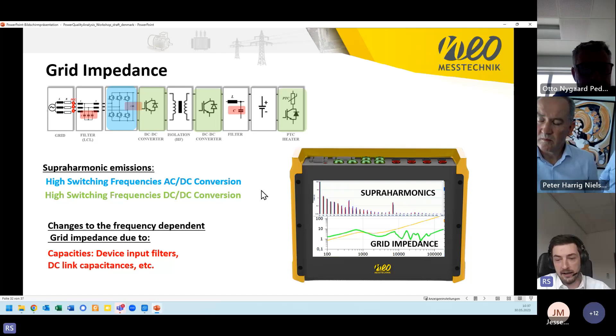I think this brings me more or less to the end, to my last slide. Regarding the energy source and the different power generation technologies—inverter, asynchronous or synchronous generators—we have power quality parameters like harmonics, unbalance, flicker, voltage changes or voltage height, and frequency behavior. But we also have new parameters, like DC parts, getting more and more important. We see this at photovoltaic parks, for example, subharmonics, supraharmonics up to 9 kilohertz or to 150 or even 500 kilohertz. We see resonances in the grid, and therefore grid impedance measurement will get more and more important.